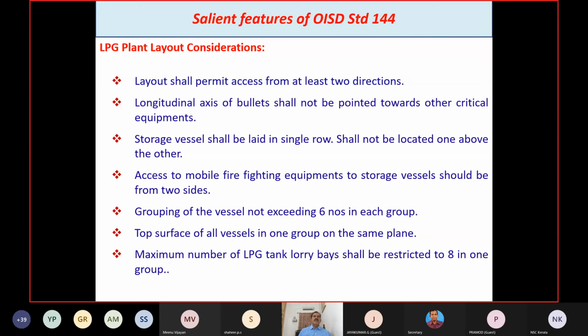So, the LPG plant layout considerations. Layout shall permit access from at least 2 directions. There should be 2 gates available for such a layout. The longitudinal axis of the bullets shall not be pointed towards other critical equipment or any control room. The storage vessels shall be laid in a single row, and shall not be located one above the other. The access for mobile firefighting equipment to storage vessels should be from 2 sides, so alternate access should also be provided.